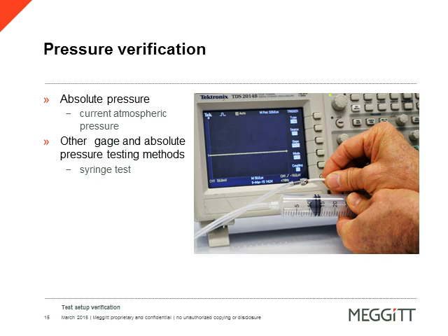I actually like this test method because it's so seemingly simple. The only challenge may be in some installations where a tube or a syringe cannot get to the mounted transducer. So this test to validate functionality of the pressure sensor itself may be done before final mounting in its measurement location.